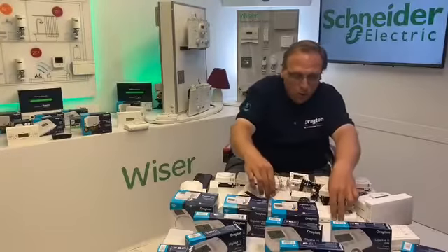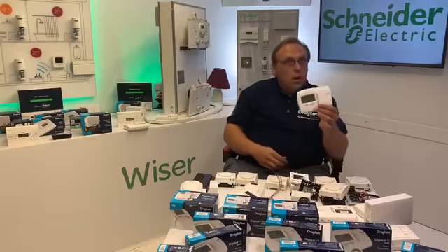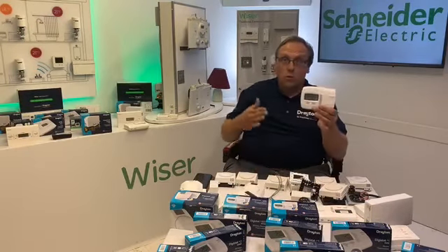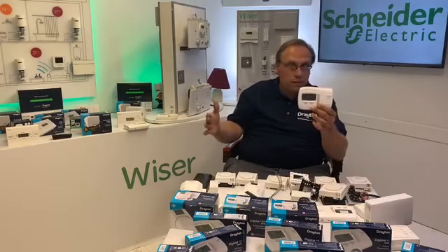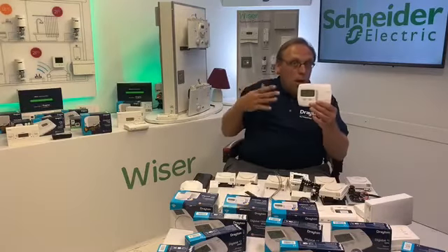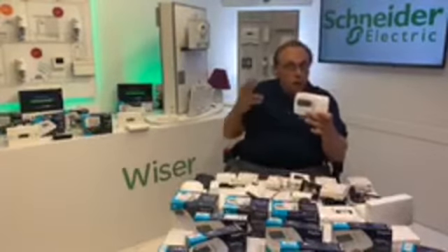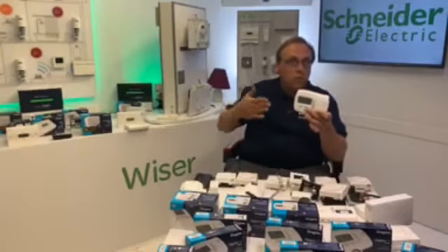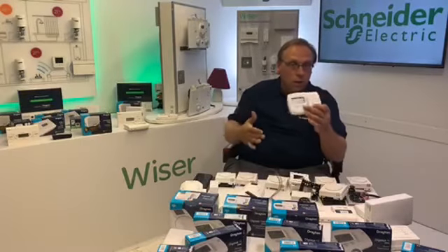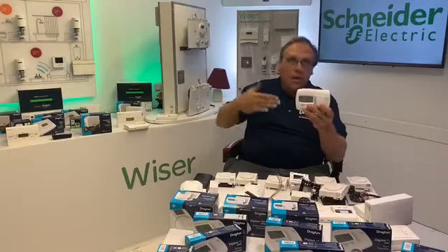So that brings us on to the Plus 2 and Digistat Plus 3. So Plus 2 is 24-hour programming, so you can have 3 periods throughout the day, or 3 ons and 3 offs, you can view it as, much like the LP, but every day would be the same. So you'd set it up once and then every day would follow the same. You can use it in manual mode as well, which is just a straightforward up and down thermostat, but if it's set to auto, it's following the schedule that you're setting, which is different time and temperature events throughout the day. Easy to program. Just keep stepping through with the left-hand arrow key, and that will take you through all of your periods.